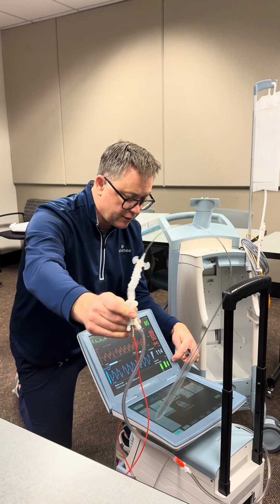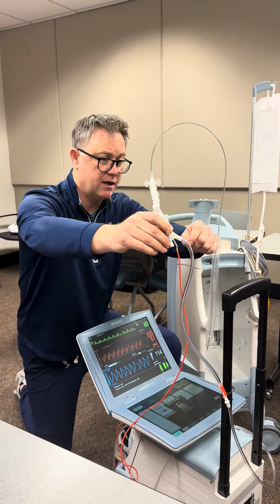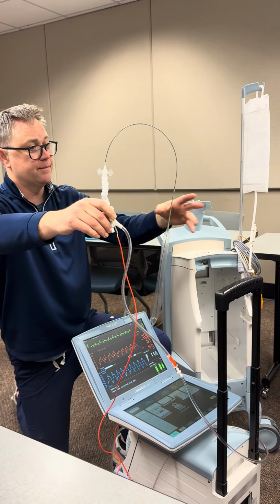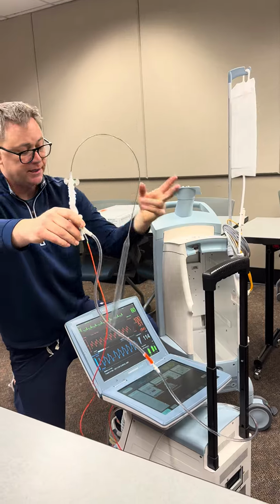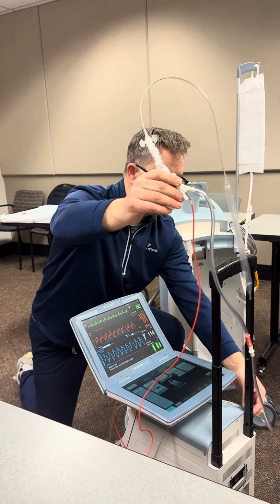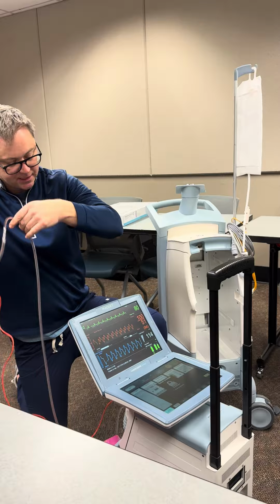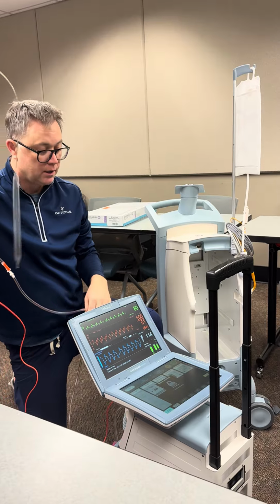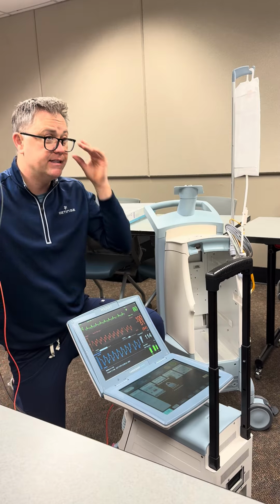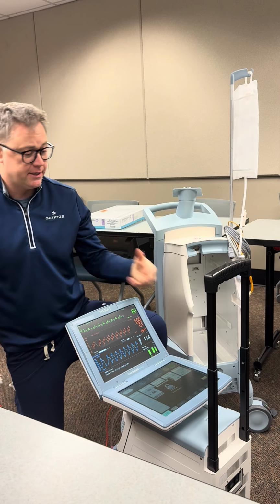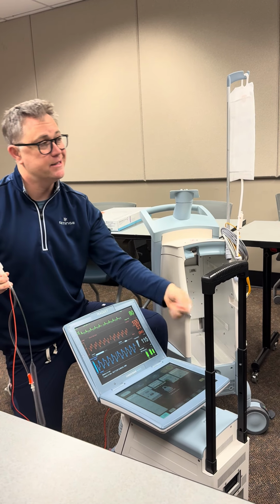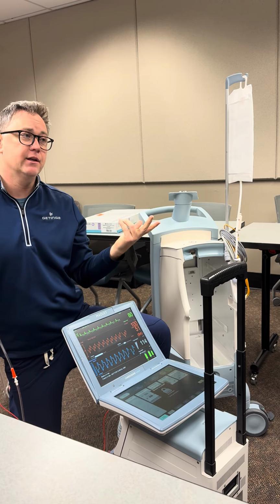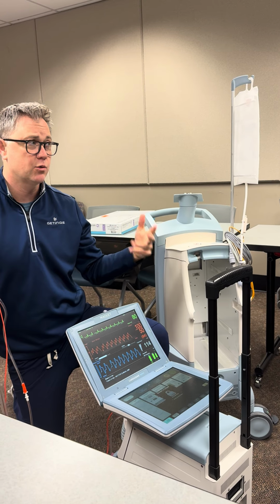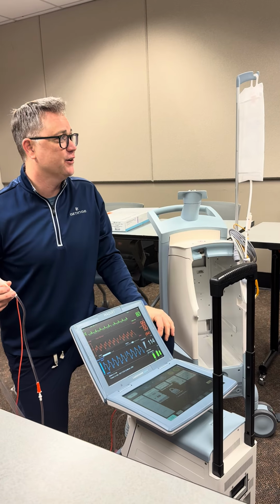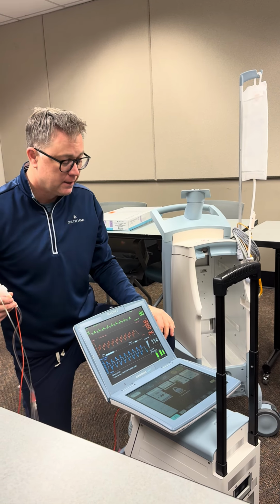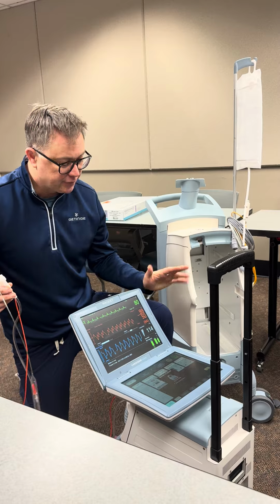So 36 autofills is basically 36 of those 2-hour intervals where it flushes the line and refills it. If you have a disconnection of this helium line, you lose 6 of those 36 autofills. So I always remind people, we've had some flight teams that have had trouble loading the patient and then loading this unit in at the same time, so they disconnect it when they get the patient in. And you can imagine if you did that 2 or 3 times, 6, 12, 18, you've lost half of your helium before you even start your transport. So just be mindful of that if you can.